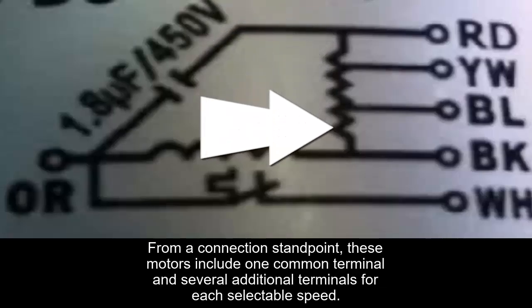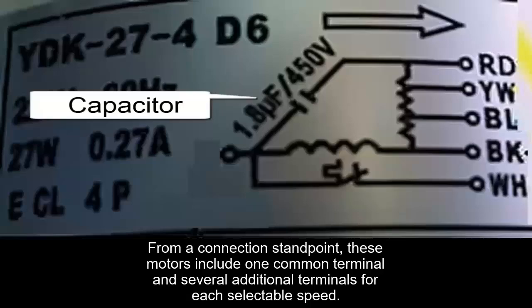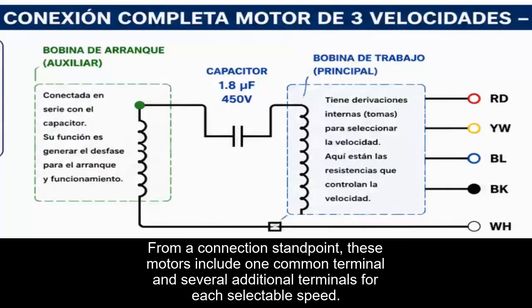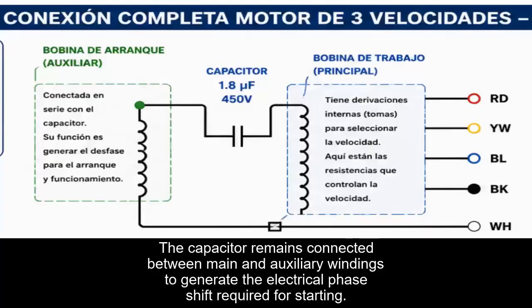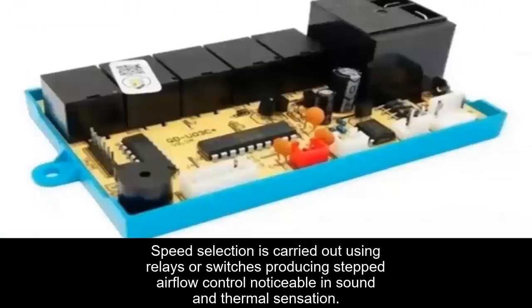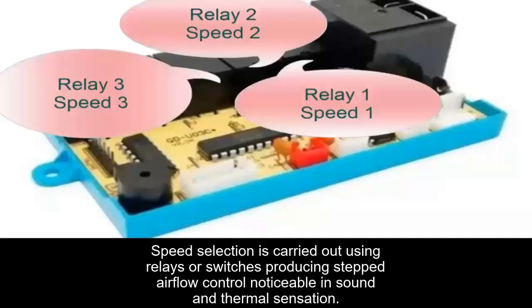From a connection standpoint, these motors have one common terminal and several additional terminals, one for each speed. The capacitor remains connected between the main winding and the auxiliary winding in order to generate the electrical phase shift necessary for starting and stable motor operation.